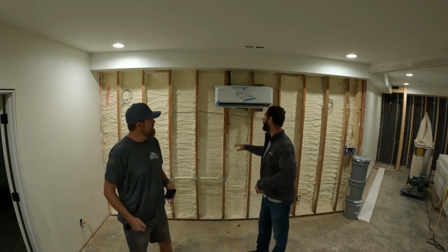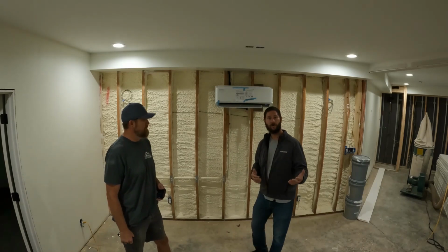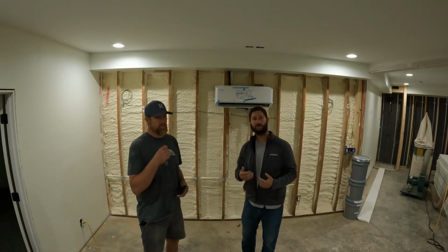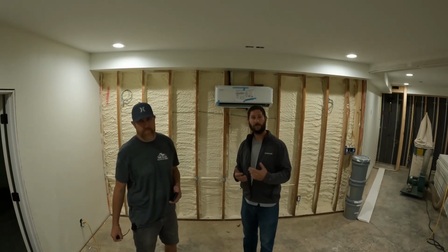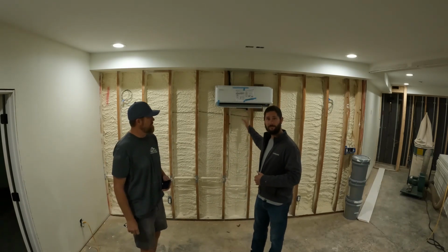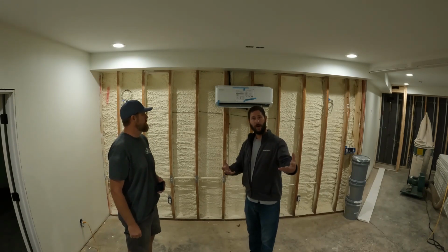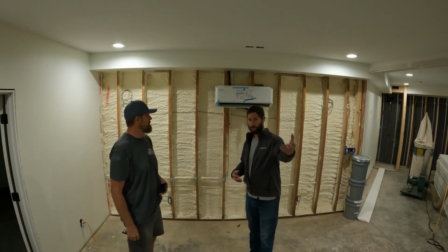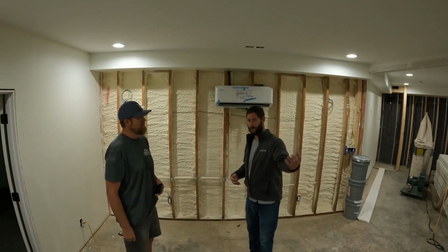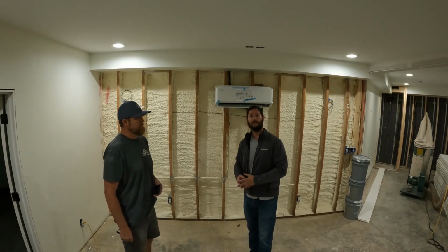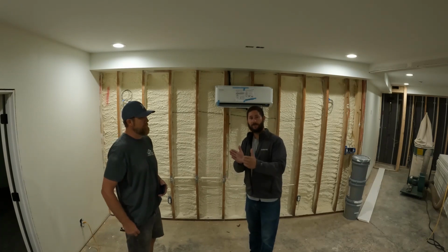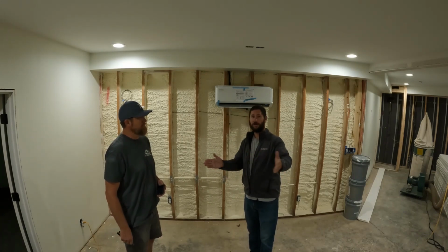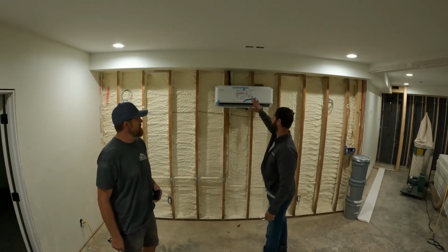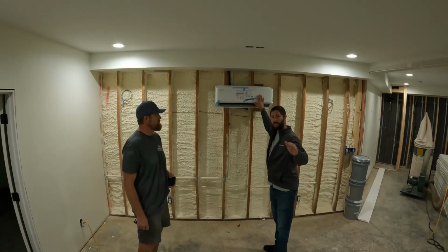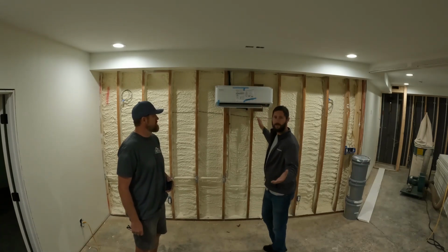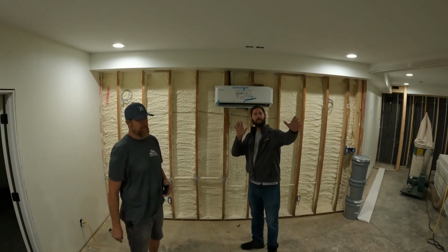The second reason that comes to mind is not having the ductwork. If you have ductwork in an unconditioned space like a crawl space or an attic, then typically you're losing 20 to 30% of your efficiency because most ductwork is not sealed properly like it needs to be. So you're automatically either pulling hot air from your attic or dirt and dust into your crawl space through your return, but then you're pushing out of your supply where all the ducts are connected, because usually it's not sealed. You're pushing all that supply out, so it's not actually going in your home. So 20 to 30% loss of efficiency with the ductwork, and then we have the ability to save all of that space in our home.